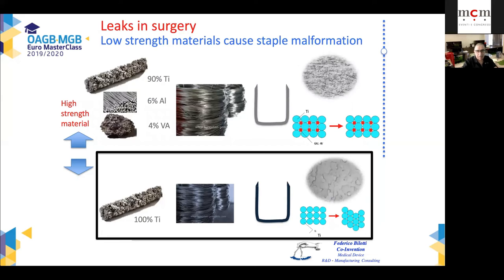The staples inside the instrument, which is the most important aspect of the instrument, are of two kinds: alloy titanium or pure titanium. Why do manufacturers choose one or the other? Manufacturers that use alloy titanium, like Johnson & Johnson, are the ones that have instruments capable to bend those staples because they're the strongest type. As you see in the image, the blue dots describe the molecules of the titanium and the red dots describe the alloy components, aluminum and vanadium, which make the alloy so strong that it's difficult to bend and also to unbend. Instead, the pure titanium at the bottom of the screen, where only titanium molecules are described with the blue dots, is easier to bend and unbend.